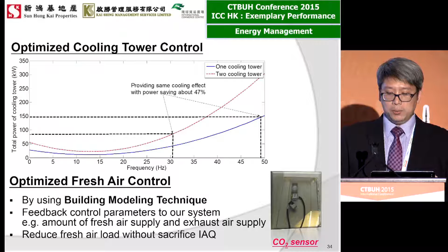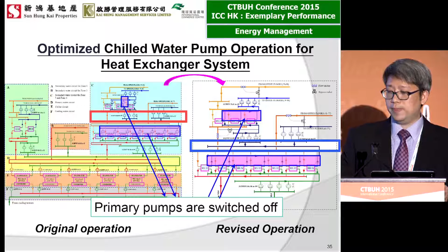Optimize chilled water pump operation for the heat exchanger system. Conventionally, the primary chilled water pump is for providing constant water flow through the system to maintain system operation performance. According to our design, our heat exchanger system maintains high performance even under variable water flow conditions, and therefore, we can simply switch off and bypass these pumps, reducing a significant amount of pump energy consumption.